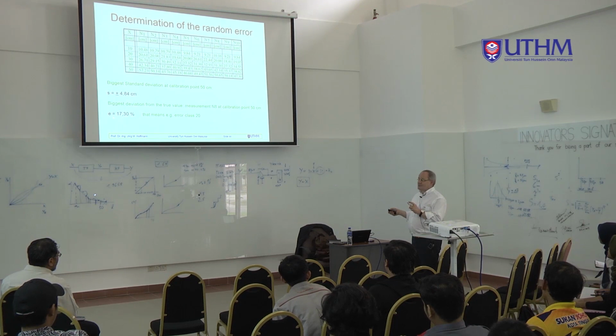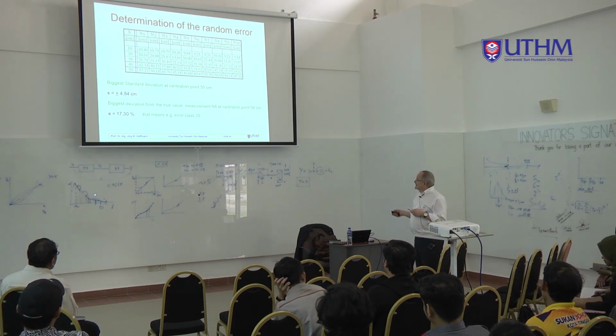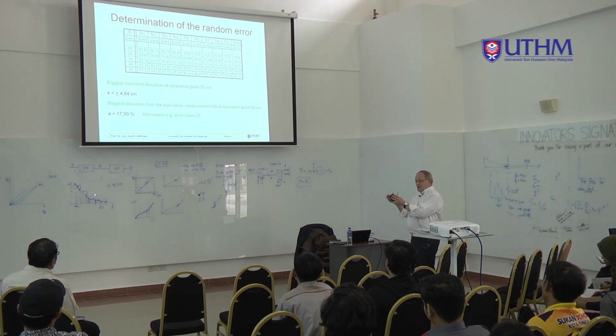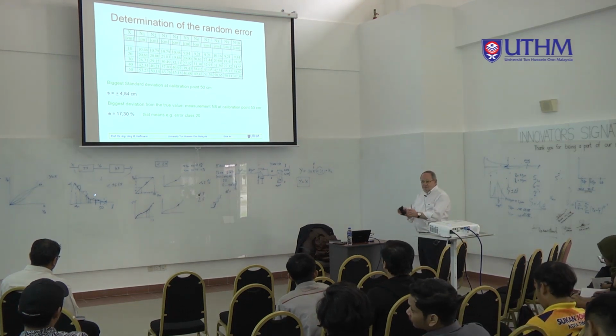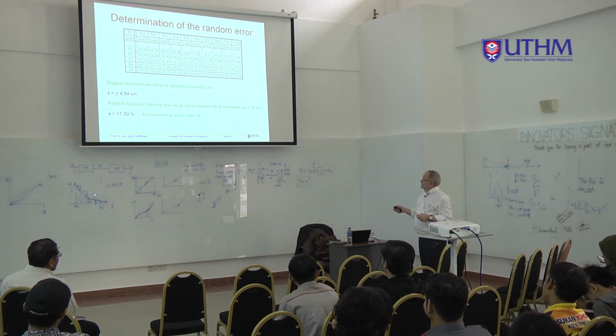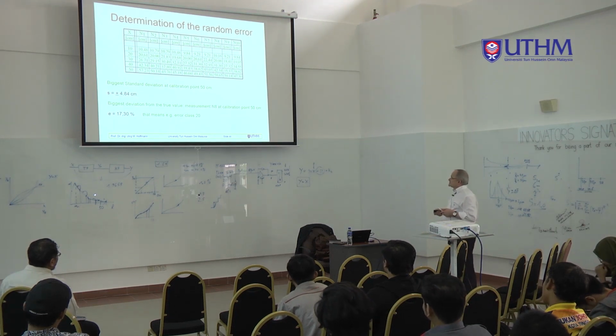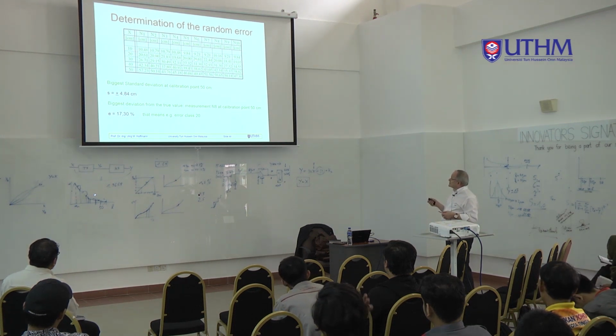That means the manufacturer says the customer should never measure a bigger value, and so he puts a little bit on top, 20%. You can also say 25%. There is no rule. Therefore, that's not a scientific method. But here you have now corrected the systematic part, you have determined the random part, you have described the random part with statistics, with standard deviation, as a scientific method, and with the error class as an industrial method. And you see here also that when you measure now again, at 20 centimeters the device should measure values around 20 centimeters, also for the future, because it is calibrated now.